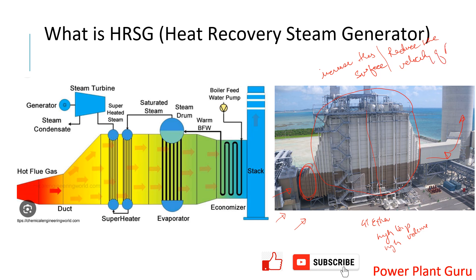Another important feature for high heat transfer is that, unlike auxiliary boiler tubes which are bare tubes, HRSG tubes have fins on the outer tube surface. These fins help capture additional heat and transfer it into the water flowing inside the tubes. This finned tube design is a key characteristic of HRSG heat transfer surfaces.